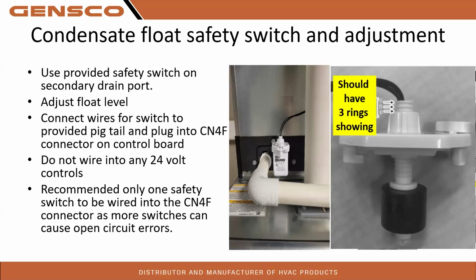The way our circuit works is it sends a 5-volt DC signal through that circuit to make sure that it's actually closed. The more safety switches you add onto that system, the more resistance you're putting on that circuit and the higher the possibility of lowering the voltage and faking the system out to think that the safety switch is actually open. So yeah, I recommend only one safety switch on there if possible.